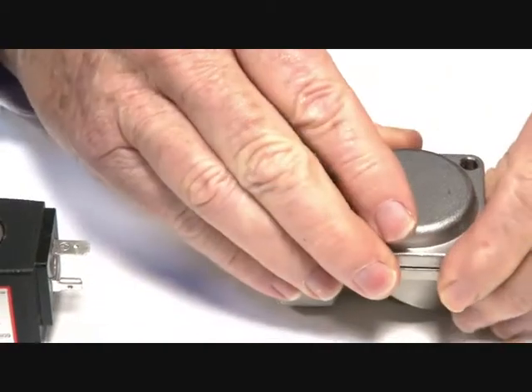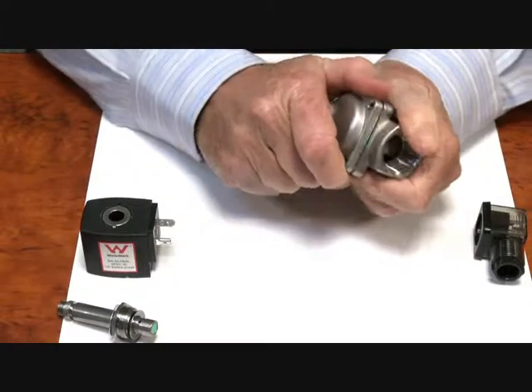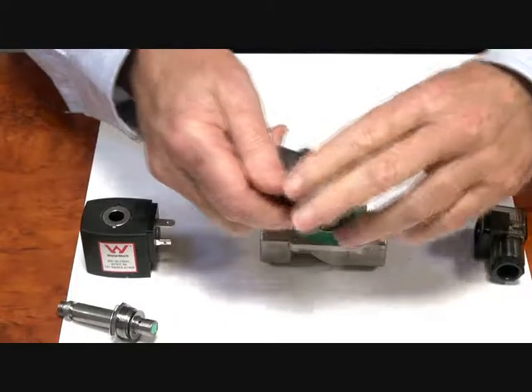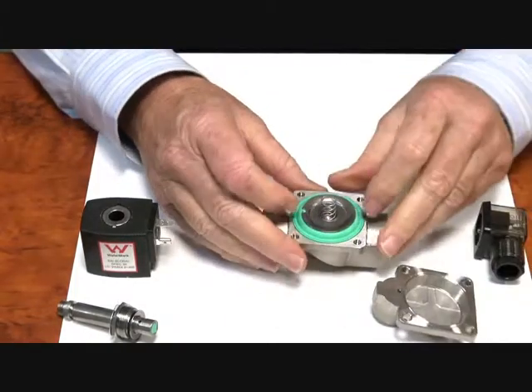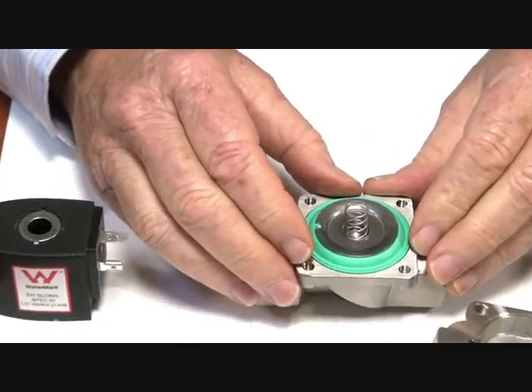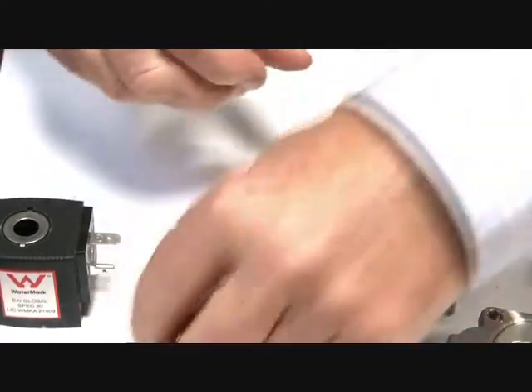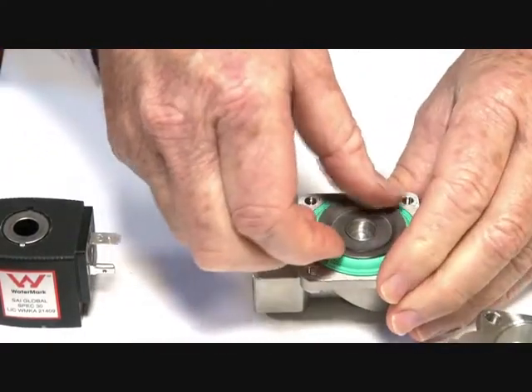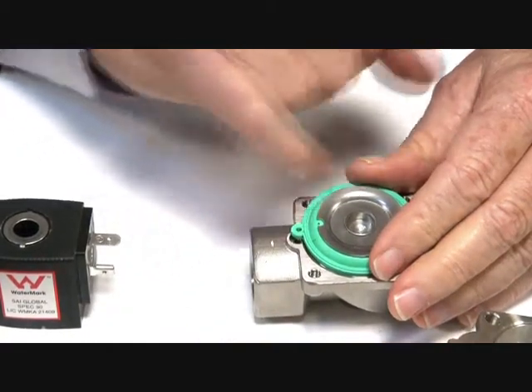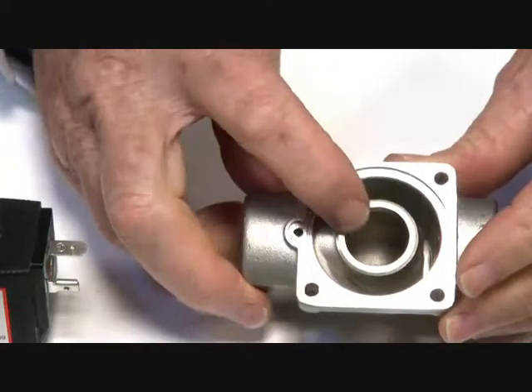The Watermark valves have EPDM diaphragm assemblies. The diaphragm with a return spring to keep the valve diaphragm closed, even at very low pressures, without leaking. There's a little jet here which equalizes the pressures, and that's the valve diaphragm itself with a seat.